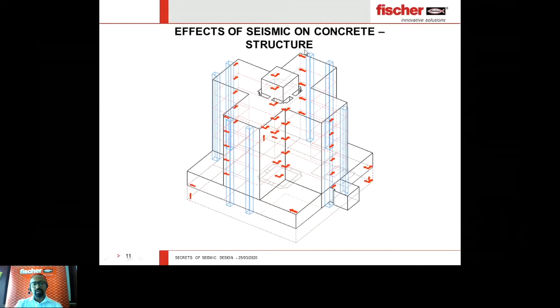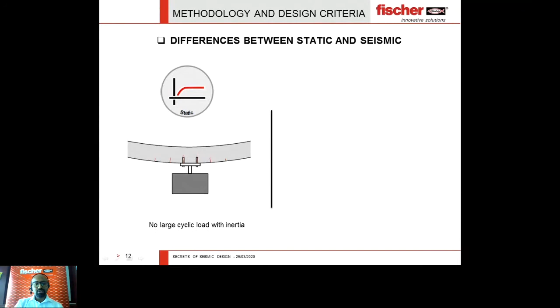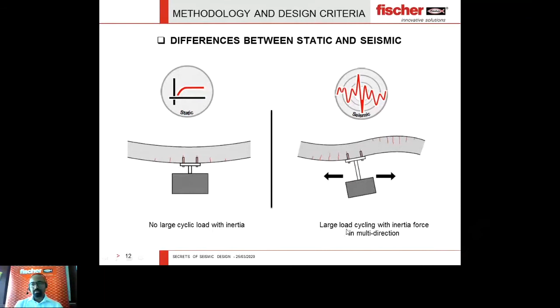Here are some main differences between static and seismic design with respect to concrete. In a static design, for example fixing an equipment under normal static load, there is little to no cyclic load. In a seismic condition, the loads might have huge cyclic action because the earthquake pushes the application in all lateral directions — this is one main difference.